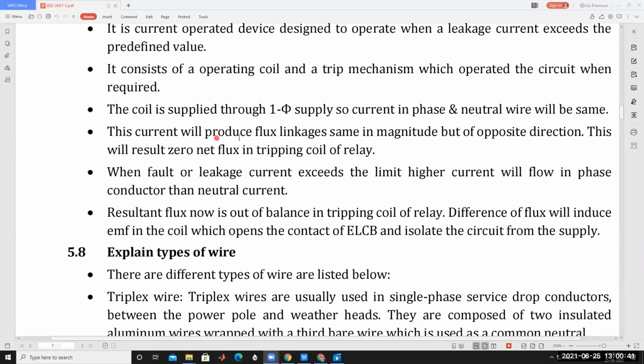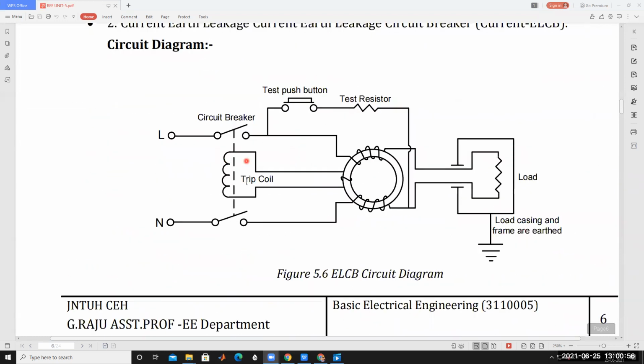The currents produce flux linkages equal in magnitude and opposite in direction. This results in net flux of 0 in the tripping coil of the relay. So 0 flux is developed in the tripping coil, because however much flux is developed here, the same amount of flux is developed by the other coil, connected opposite to each other.